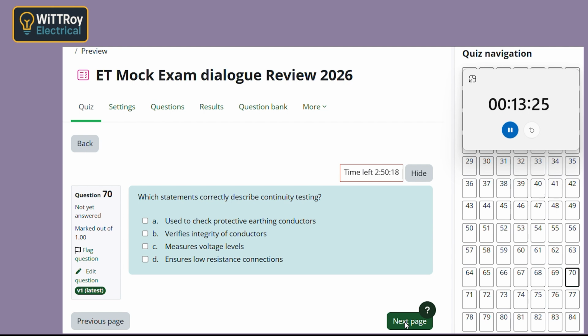Question 70. Which statements correctly describe continuity testing? Checking if conductors are connected? Yep. More specifically, you're checking that there's a low resistance path. So if resistance is high, something's wrong. Exactly. Maybe a loose joint or broken conductor. And it's important for earth conductors too. Very important. You need a good earth path for protection to work properly.